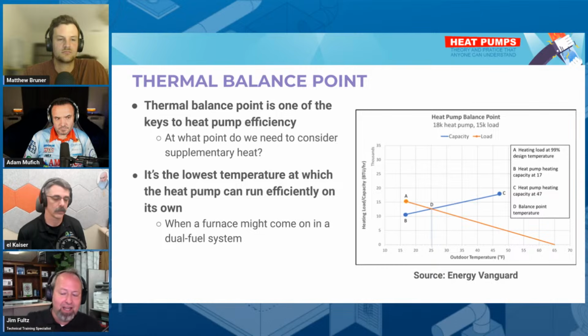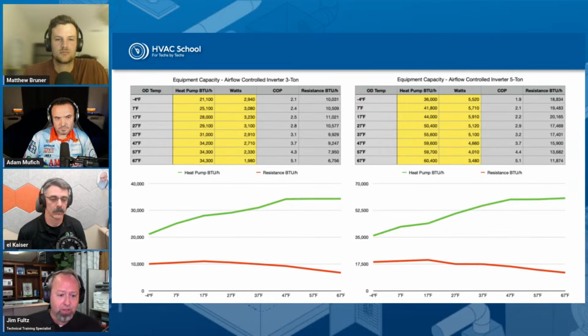All right, let's head back to that other one, because that other one's really where I want to focus on. And with that, I would probably put another column on this chart. We have the resistance BTUH, and we could put another column on there that would deal with the amount of gas or fuel that a gas furnace would take at those same levels. And so just to try to make this a little easier to understand here, we know that the balance point for efficiency between resistance heat and the heat pump is that COP of 1. Eric did a wonderful job of defining that, but it's different for a gas furnace.